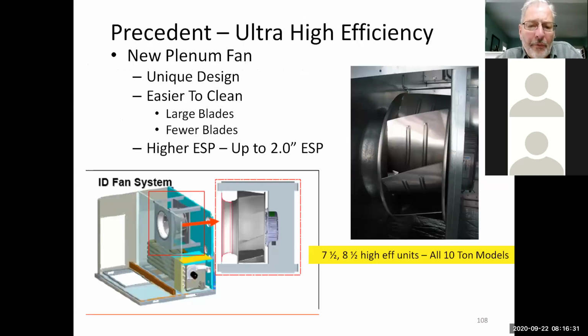Now on these units, we've got what we call a plenum fan. A plenum fan is a backward curve fan, and if you look at this, the fan turns counterclockwise. It draws the air in, but it paddles it. It's not like you'd think, it doesn't scoop the air. It paddles it. And again, these will operate up to 2 inches of static also. But they're lighter. They're keeping the weights down in the units, and they move a fairly good amount of air in a pretty efficient way. It's on our 7.5, 8.5 high efficiency units and on all 10-ton models.